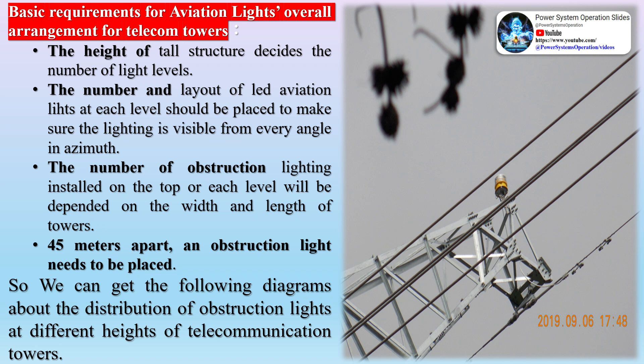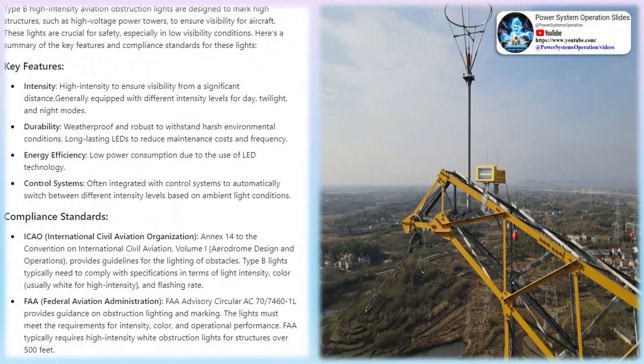For example, buildings and facilities above 45 meters are equipped with multi-layer medium- or high-intensity obstruction lights, and low-intensity obstruction lights can be set between them. The low-intensity obstruction light is red with an effective light intensity of 100 candelas ±25%. Medium-intensity aviation lights are generally used for tall structures ranging from 45 meters to 150 meters in height.